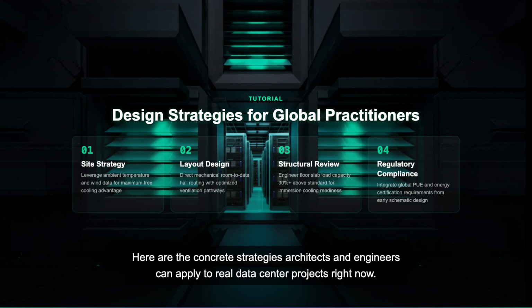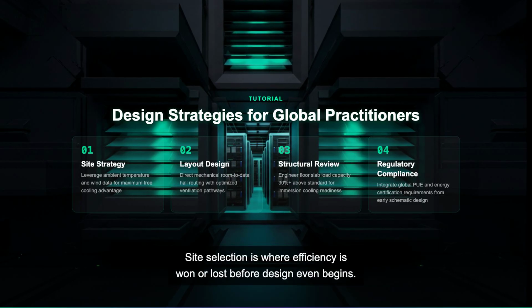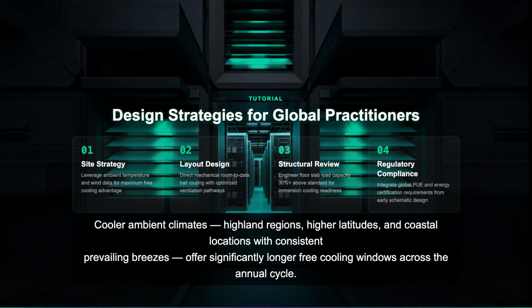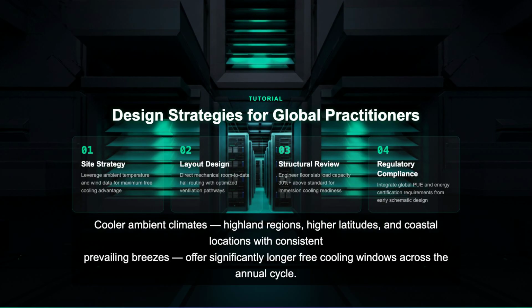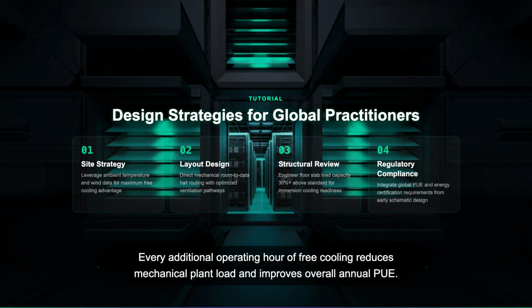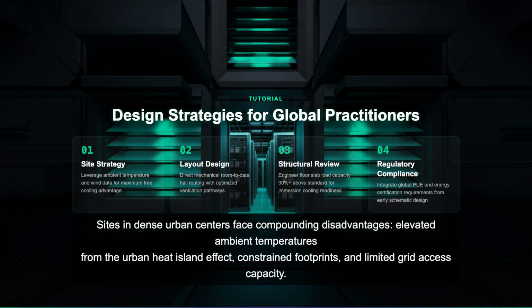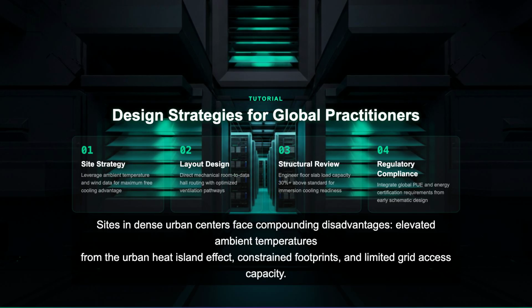Site selection is where efficiency is won or lost before design even begins. Cooler ambient climates, highland regions, higher latitudes, and coastal locations with consistent prevailing breezes offer significantly longer free cooling windows across the annual cycle. Every additional operating hour of free cooling reduces mechanical plant load and improves overall annual PUE. Sites in dense urban centers face compounding disadvantages: elevated ambient temperatures from the urban heat island effect, constrained footprints, and limited grid access capacity.